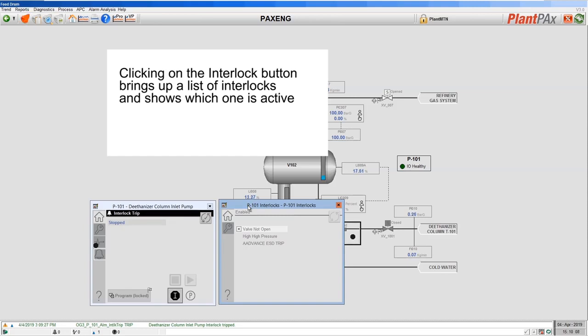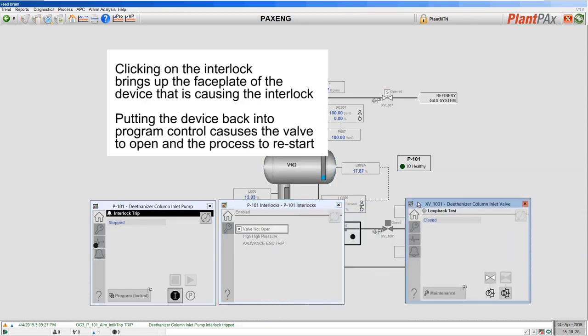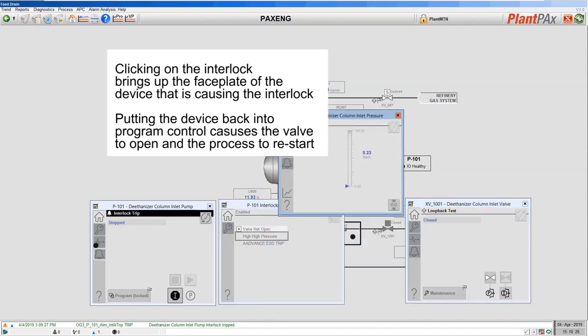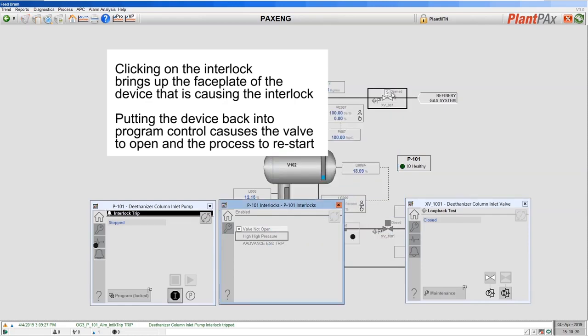From the pump faceplate I can bring up the interlock faceplate, which shows me the interlocks that are active for the pump. Now I can see that the 'valve not open' interlock is active. From this interlock faceplate I can then link directly to the causing device — by clicking on the 'valve not open' interlock I can bring up the faceplate for the valve that's causing it, and if I clicked on the high-high pressure interlock I'd bring up the analog input that causes that. At the moment the 'valve not open' interlock is present, so I need to get the valve open to start my pump.